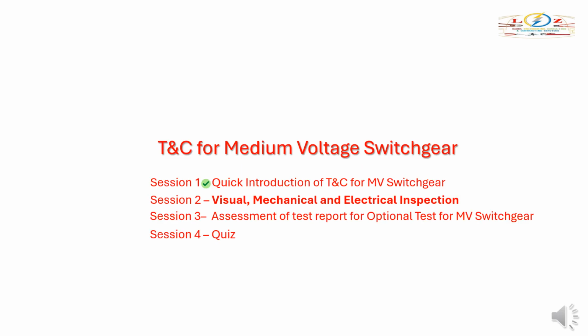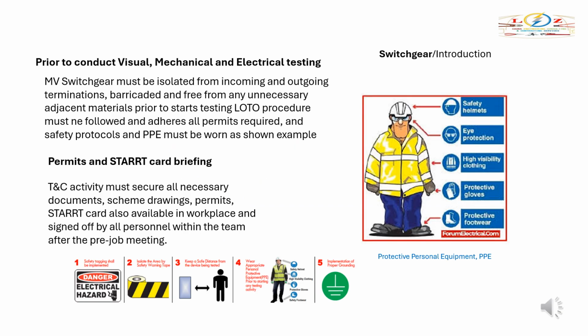Testing and commissioning for medium voltage switchgear. Previous Session 1 was a quick introduction of MV switchgear. Now Session 2 covers visual, mechanical, and electrical testing and commissioning inspection based on project specifications and adopted codes and standards. Prior to conducting visual, mechanical, and electrical test inspection, MV switchgear must be isolated from incoming and outgoing terminations, barricaded and free from any unnecessary adjacent materials prior to starting testing.